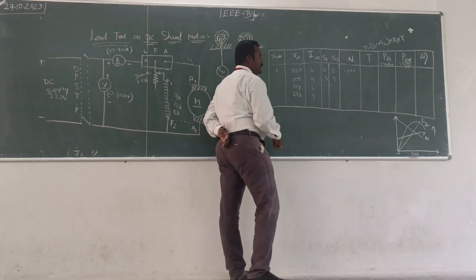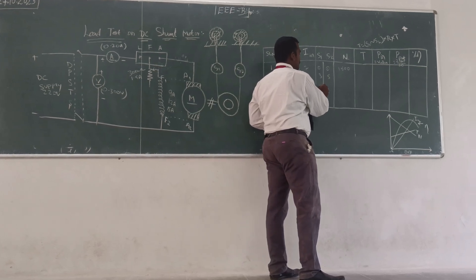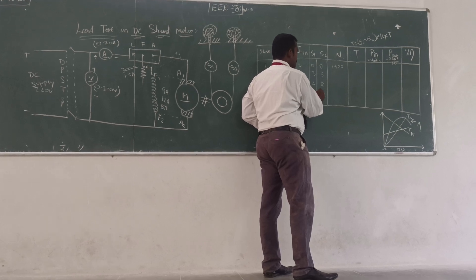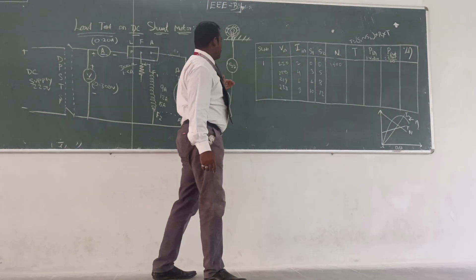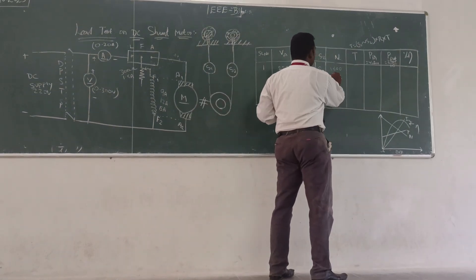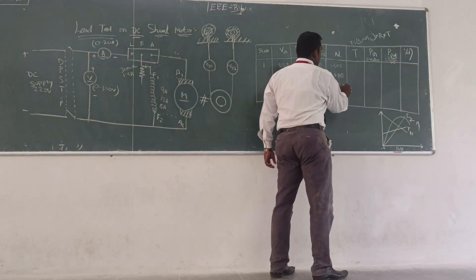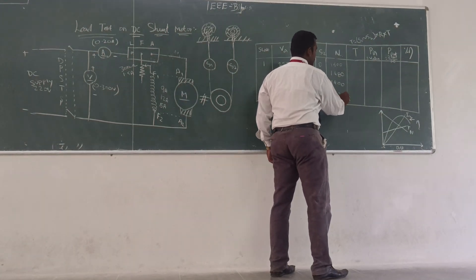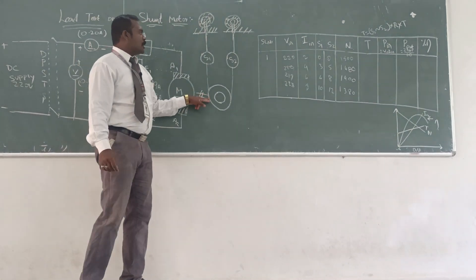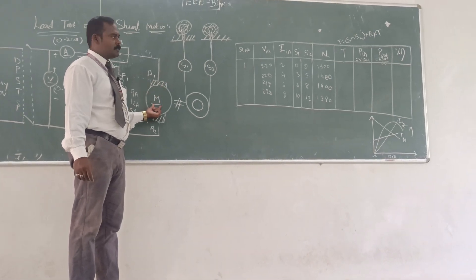Whatever reading you get, note that down. Similarly, the spring balance readings may be 6, 8, 10, 12, and so on. At the same time, while you are applying the load, the speed is also getting reduced — 1480, 1400, 1380. The speed is actually getting reduced because it is the DC shunt motor; while applying load gradually, the speed keeps going down.